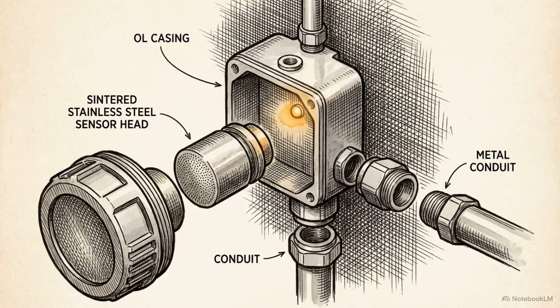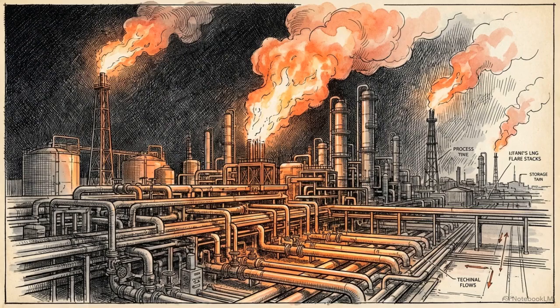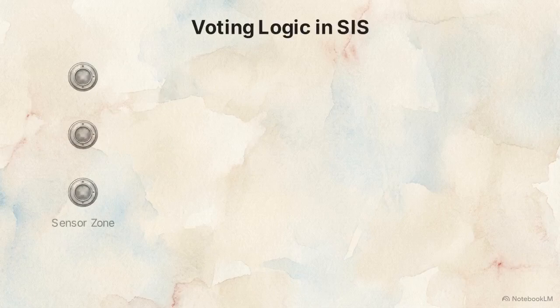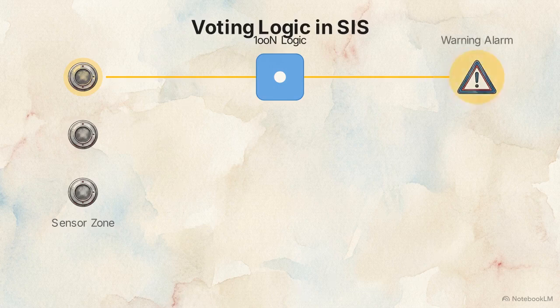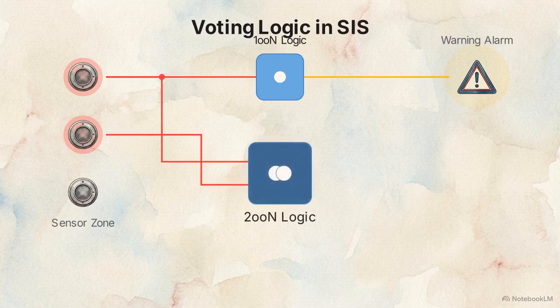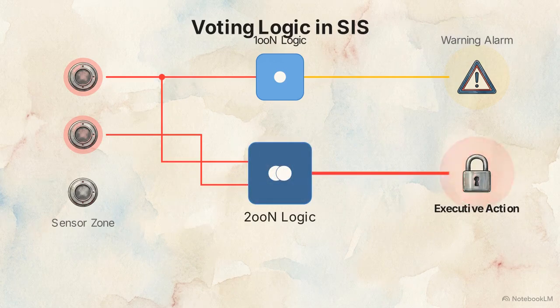Once the physical sensor detects the gas, it does not immediately order a total facility shutdown. A false shutdown on a large-scale LNG facility causes immense flaring and restart delays, costing up to $10 million in a single day. To prevent false shutdowns, engineers use voting logic. Under 1 out of n logic, a single spiked detector only triggers a warning alarm. An automatic shutdown requires 2 out of n logic, where 2 independent detectors simultaneously confirm the exact hazard to trigger executive action.